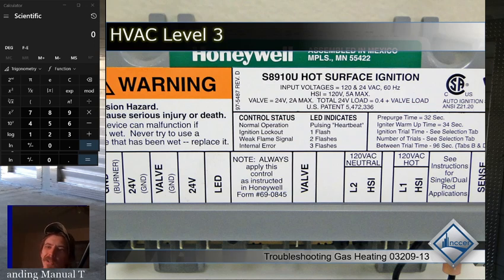But if you don't get either, but you think the thermistor really isn't working right, you can stick the thermistor in a glass of ice water, which should be 32 degrees, right? Measure the resistance, then find the chart for that thermistor and make sure the resistance you get is what it's supposed to be at 32 degrees. If it's not extremely close to that, then something's wrong with the thermistor and it's reading temperature wrong. That is the easier way to do it. I don't think I've ever actually had to calculate voltage drop across it to test it. I don't think I've ever had a thermistor that wasn't just open or shorted.